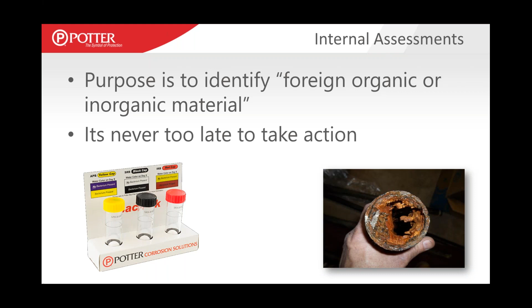Remember, I said that all the guidance for how to comply with this section is now in the annex. One of the things you can do to comply with NFPA 25 Chapter 14 is as simple as taking a water sample and testing it for certain things. The key to this, in my opinion, is that it's never too late to take action, whenever you discover the problem, and often that problem is related to corrosion. We know corrosion is a significant problem. If you ask 10 owners what's the biggest problem with their sprinkler system, 9 of them are going to tell you it's corrosion. It's never too late to do something about corrosion. There's always a solution to solve the corrosion problem. So that's important to keep in mind. But the real key here is to make sure we're assessing that internal condition at least every 5 years. That's a key to the health of the sprinkler system.